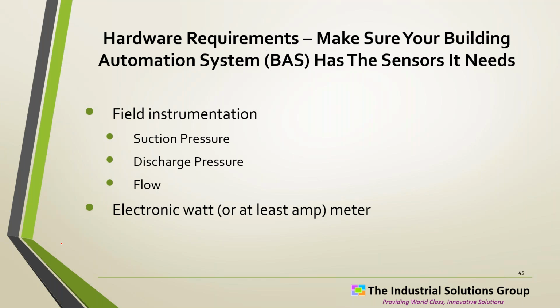What do we need in the way of hardware? Some field instrumentation: pressures, flow meter, really important to know flows. Electronically, a watt meter or at least an amp meter, and then that gives us some cross checks to check the calibration.